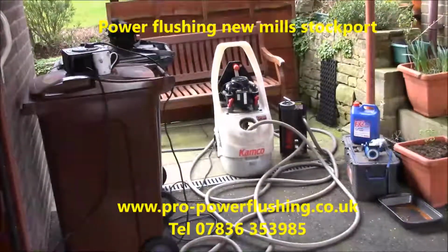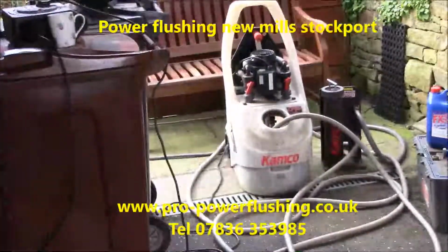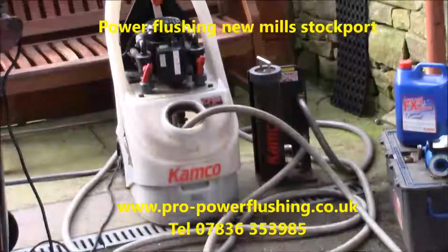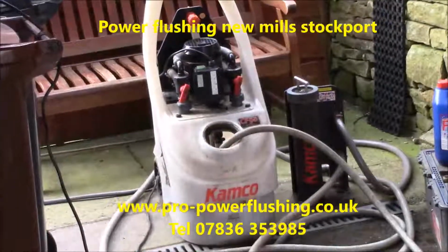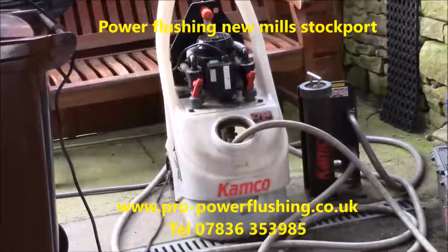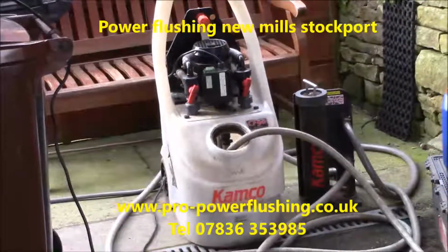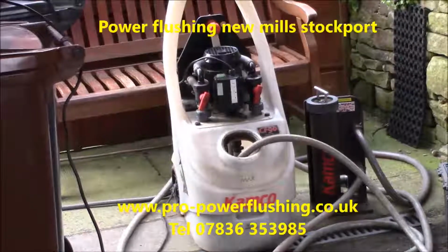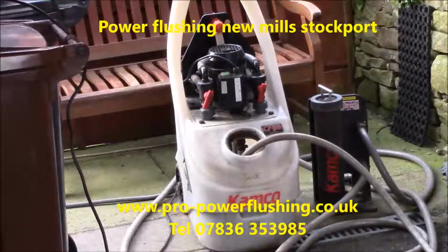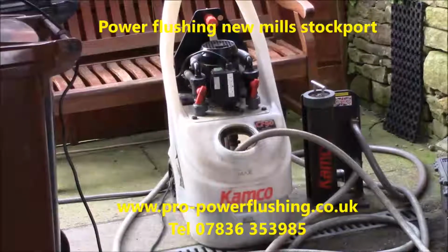We go to so many systems that have completely broken down due to the rust and corrosion in the system. We've seen boilers that are 2 months old, completely written off, because all that rust and corrosion has got into the heat exchanger and blocked it. The heat exchanger is overheated to the point of no return, and it's written off other parts of the boiler as well. That's because the installers have fitted the boiler and not power flushed the central heating system. We know a lot of central heating guys who do that. It's not good.